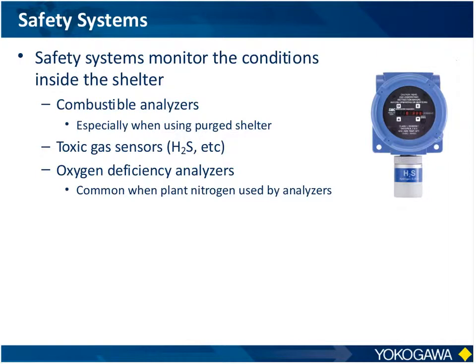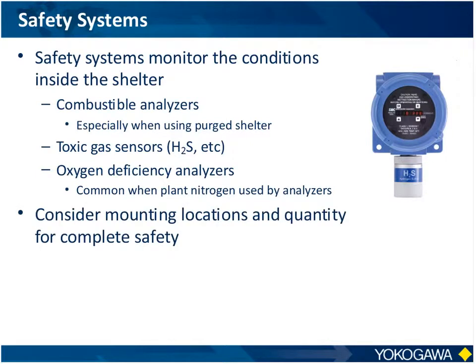And finally, you might need oxygen deficiency analyzers, especially if you're using plant nitrogen, because it's always possible that the plant nitrogen might leak and displace all of the breathable air inside there. So you want to make sure you have a safe environment for the technicians in there. As always, it's important to think about where you mount these different sensors, at different heights and locations, so that you pick up any little pockets or pools of the gases.